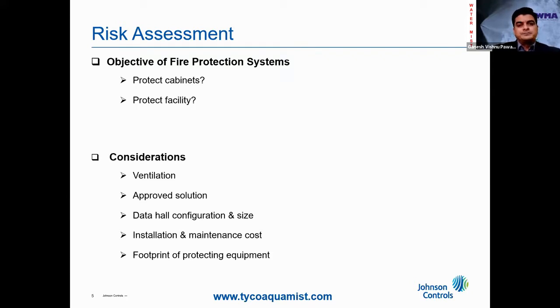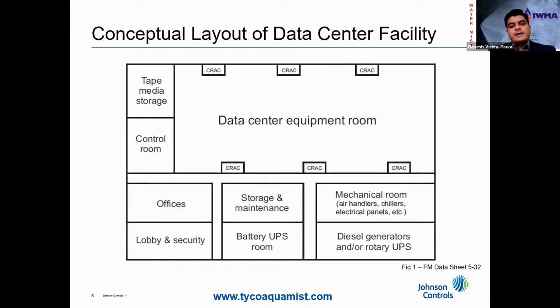data center facility. Whenever we take any data center building, typically it will consist of a data center equipment room. It will have various storage and maintenance rooms, battery UPS rooms, light hazard occupancies such as offices, lobby areas, security areas, control rooms, and mechanical rooms, which will consist of air handlers, chillers, mainly the HVAC equipment, and electrical panels. And we will also see rooms such as the diesel generator or rotary UPS rooms.